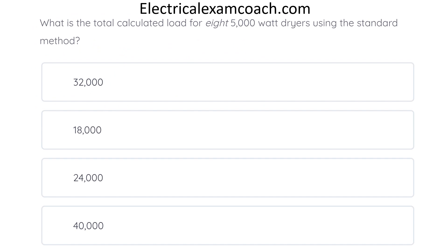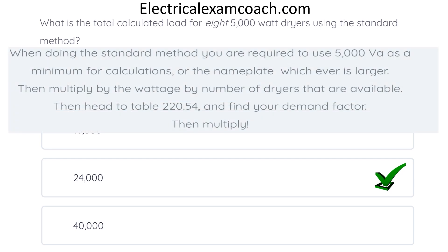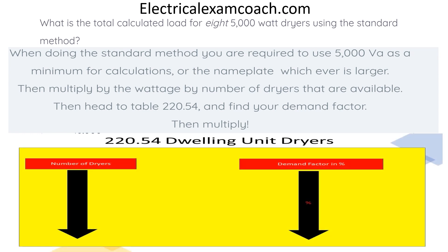What is the total calculated load for eight 5,000-watt dryers using the standard method? The correct answer is 24,000. When doing standard method calculations, we're required to use 5,000 VAs as a minimum per dryer, or the nameplate, whichever is larger. Then we multiply that individual wattage by the number of dryers we have. Then we head over to Table 220.54, find our demand factor, and multiply.